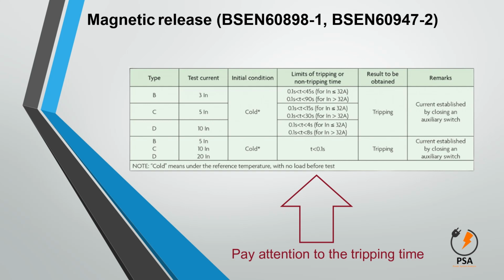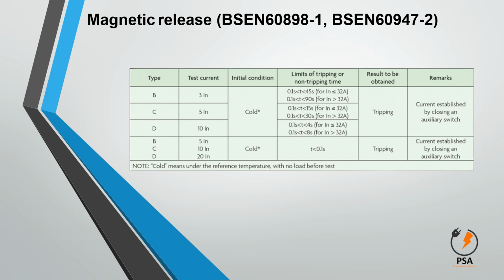D curve. In this, the CB trips when the current is between 10 to 20 times the full load current. Type D MCB is suitable for industrial applications, like transformers, X-ray machines, large battery charging systems, large winding motors, discharge lighting, etc. There are also other curves for MCBs that are used for specific applications.